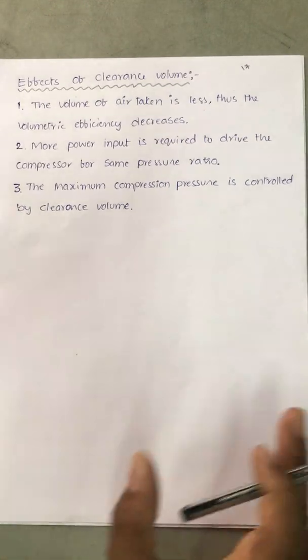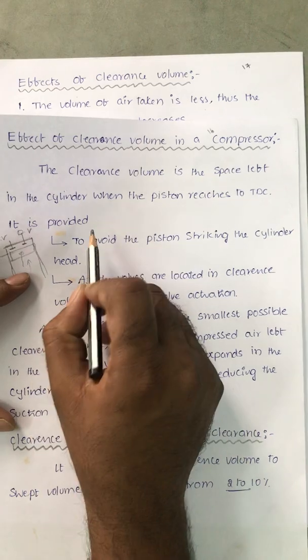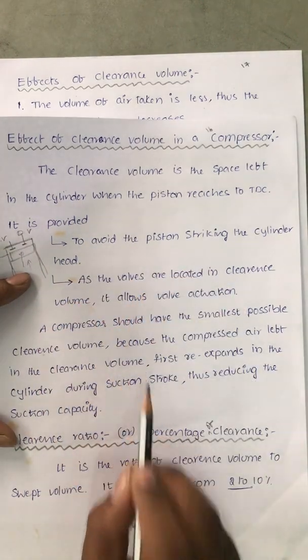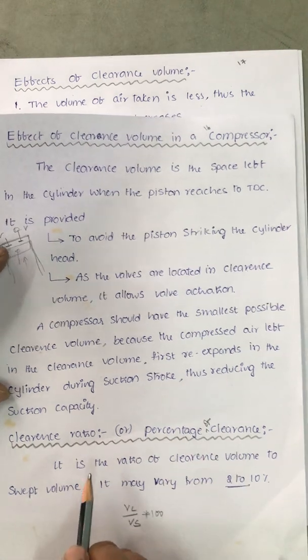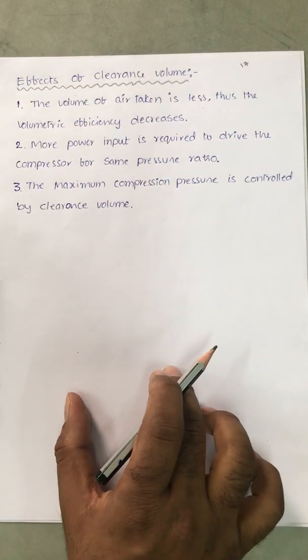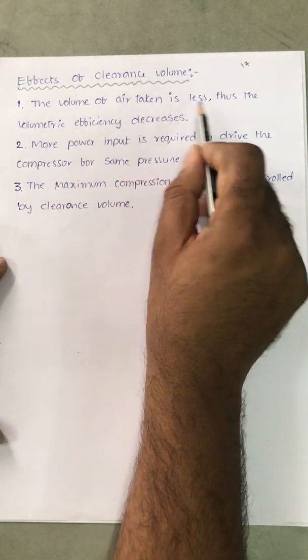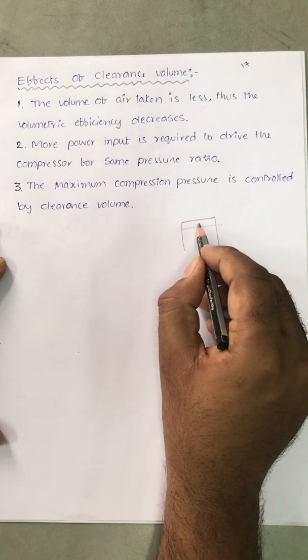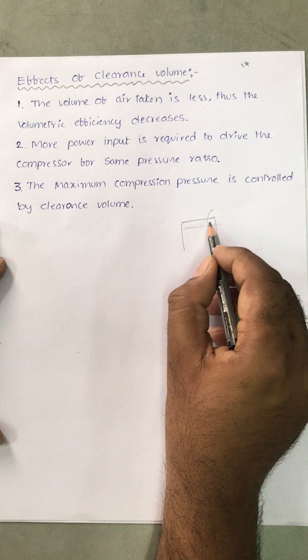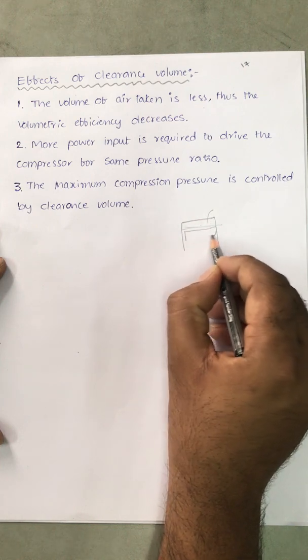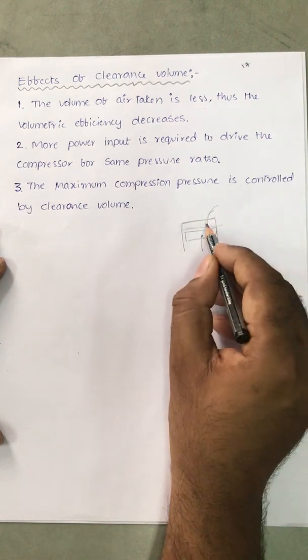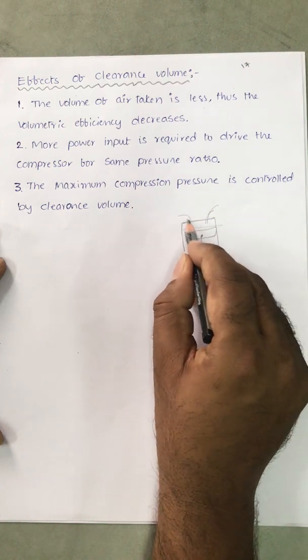Now we need to discuss the effects of clearance volume. The first effect is that the volume of air taken in is less. Because clearance volume is provided, in the compression stroke the air inside the clearance volume remains inside and does not exit. So in the suction stroke, the amount of air taken in is reduced.